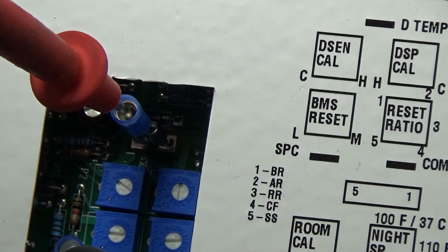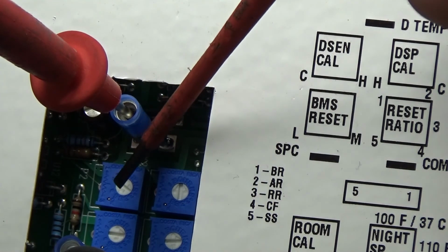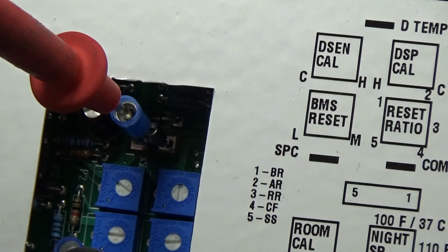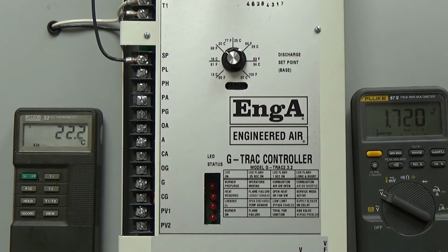To calibrate the discharge air sensor, locate the pot labeled DSEN Calibration. Using a pocket screwdriver, adjust the pot labeled DSEN Calibration until your multimeter on your right matches the multimeter on the left. Once the numbers match, you have calibrated your discharge air sensor.